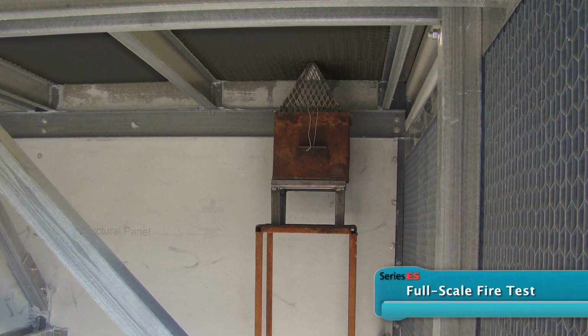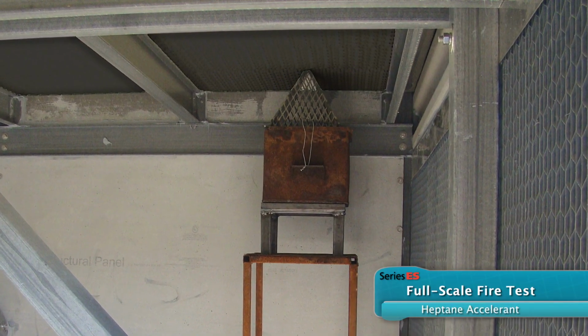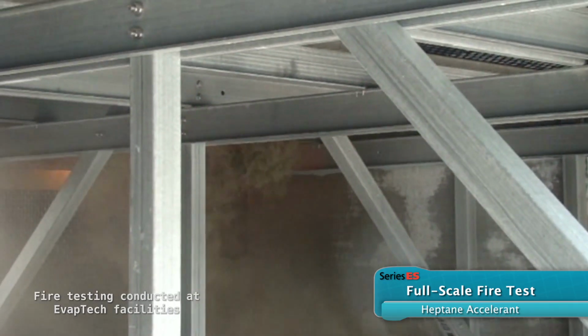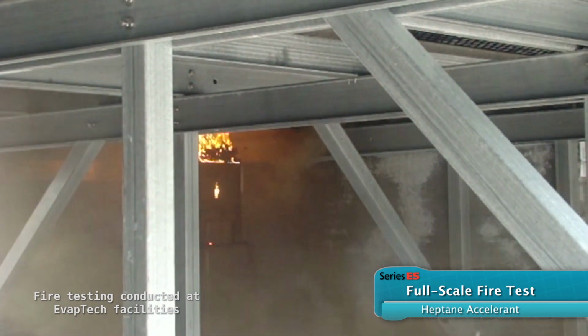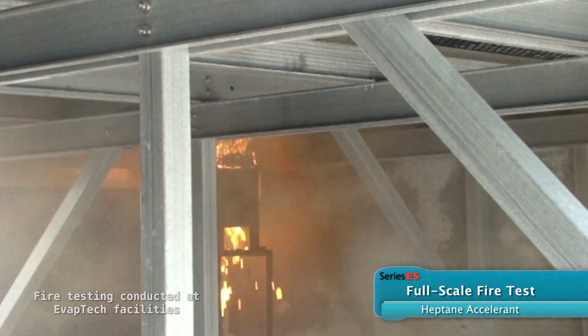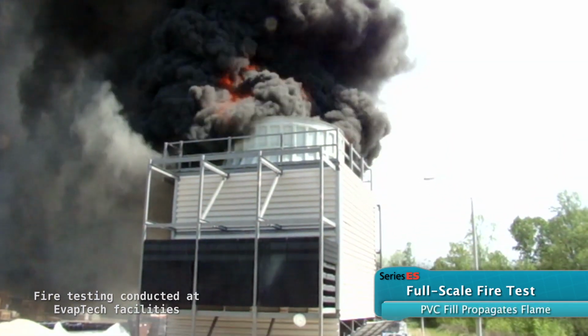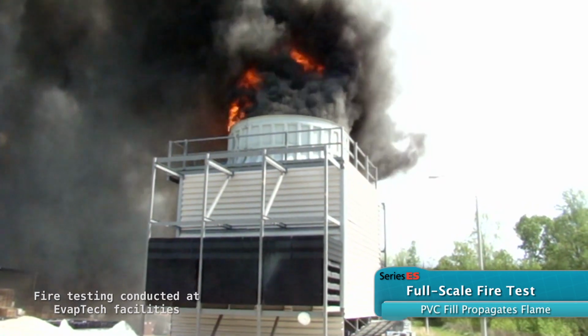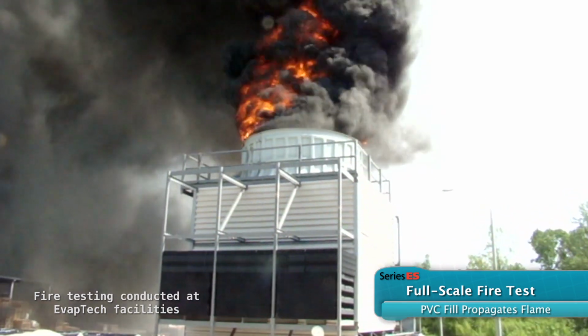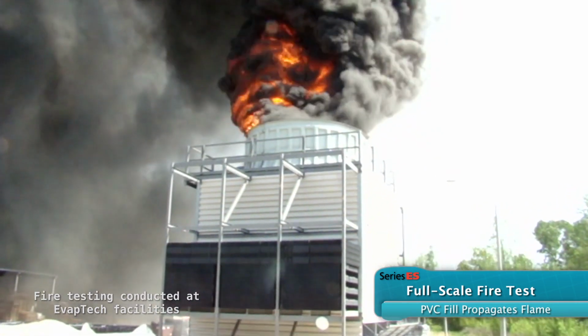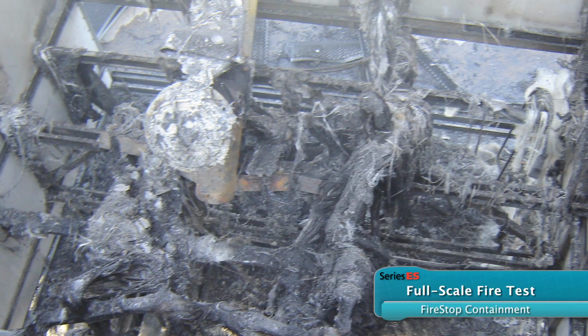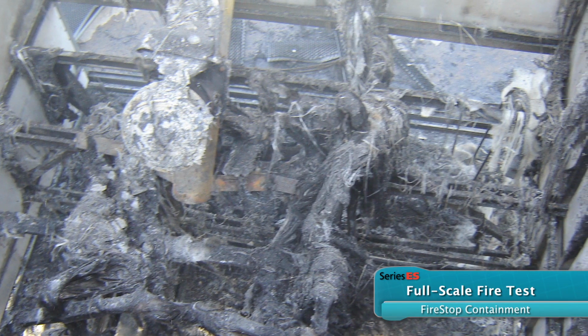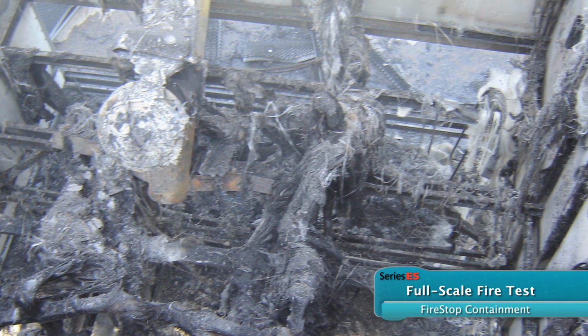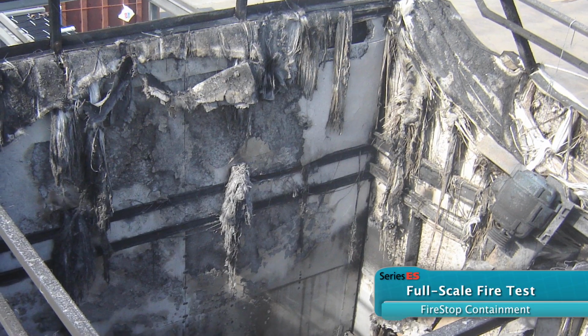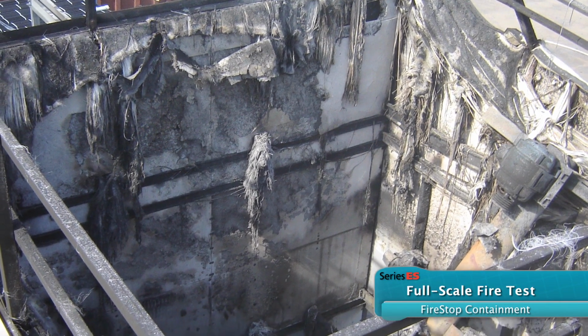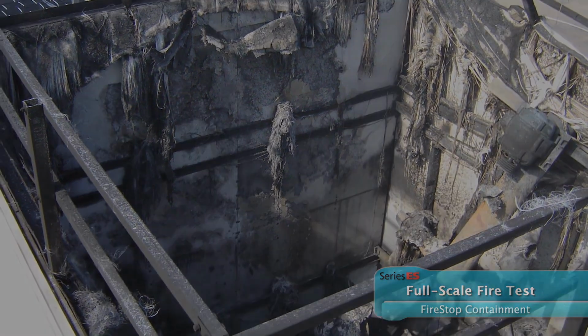The burn test starts with the pan of heptane underneath the fill. Heptane burns extremely hot, and the volume is such that it burns for 20 to 30 minutes. The PVC fill propagates the flame throughout the whole cell, and the entire inside of the cooling tower is burned away. To keep the fire from propagating to the adjacent cells or outside the cooling tower on the sidewalls, FireStop is installed around the perimeter of the cooling tower cell.